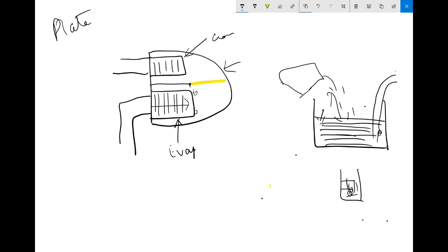If you want to do chemical cleaning, again you can do the same way which I was telling you. For a condenser, it's very easy here. Just find a point where there are two pipelines going, one inlet and one outlet. You can do it that way, but normally for a plate type heat exchanger, we always prefer to do it by removing the plates out.